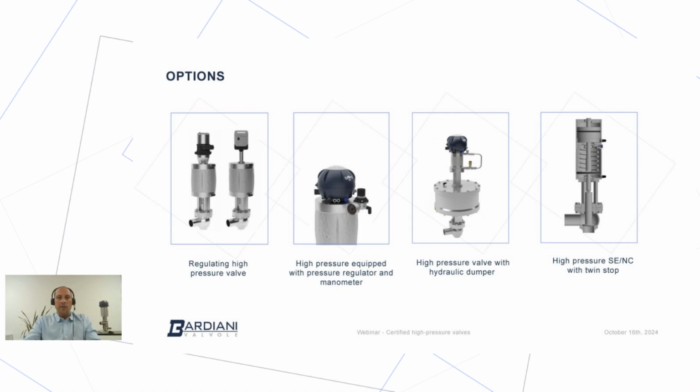There's a limited number of options available for the high pressure valve, but they are very significant. Whenever there's a need of regulating a high pressure system, we can have an electropositioner mounted on top of a high pressure actuator. So we are able to regulate or adjust a flow based on a 4 to 20 milliampere signal coming from any device in the field. For example, we need to adjust a flow in terms of flow rate, or we need to adjust a temperature by closing or opening a little bit the valve. An electric positioner fitted on a high pressure valve could be a good solution.